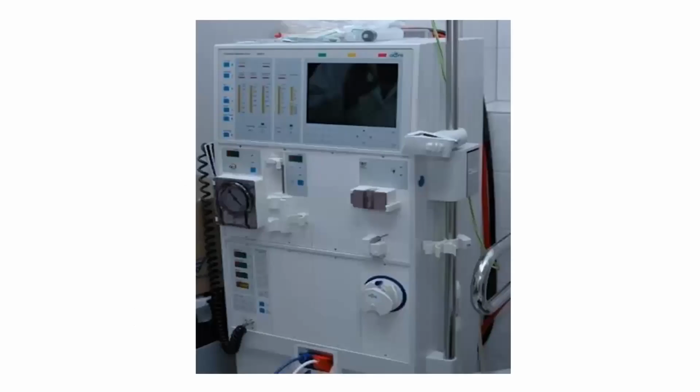Now, this is a photograph of a dialysis machine. There are different types of dialysis machines available. As I have already said, unless and until you look at the actual procedure, you won't be able to appreciate the various things performed. This is a dialyzer. It has got thousands and thousands of minute capillaries, and then these capillaries are enclosed in an outer casing. Now, the outer casing is a dialysate compartment, and in these capillaries, blood flows.